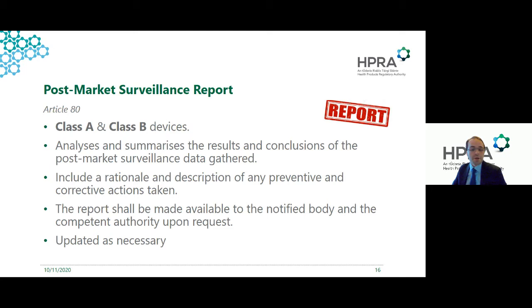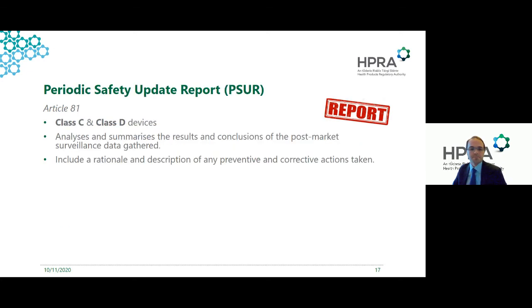For Class A and Class B devices, the report is made available to the notified body where applicable, and the competent authority may request a copy, and you update this as necessary. There's not a defined timeline on when you need to update this—it's really a dynamic process.